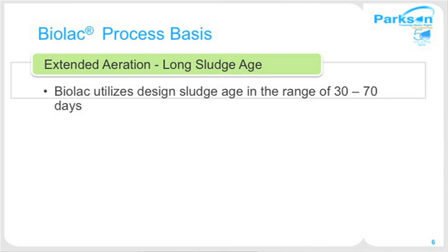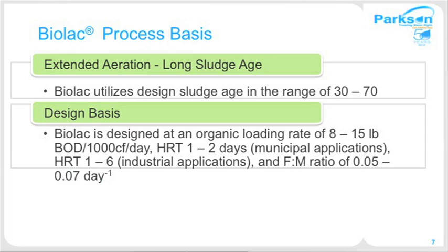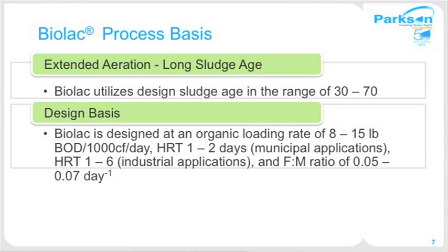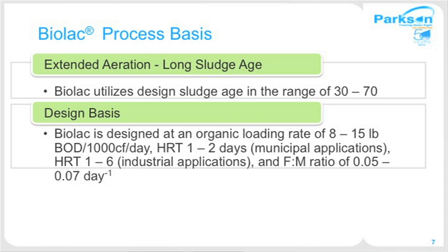Some of the design bases for the BioLac process: it's an extended aeration, long sludge age process. The sludge age or MCRT for the BioLac process is 30 to 70 days. The organic loading is typically around 8 to 15 pounds of BOD per thousand cubic feet of volume per day. It's a longer hydraulic retention time of one to two days, and in some industrial applications the HRT can go up to six days. Food to microorganism ratio is within the typical extended aeration range: 0.05 to 0.07 pound of BOD per pound of biomass.